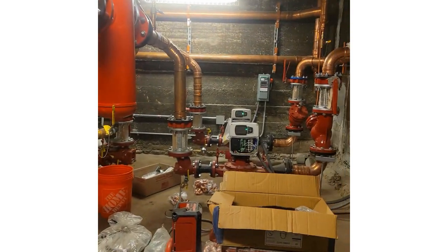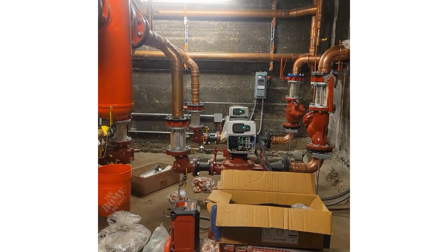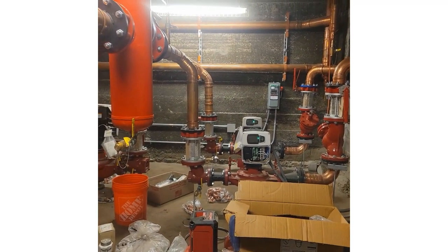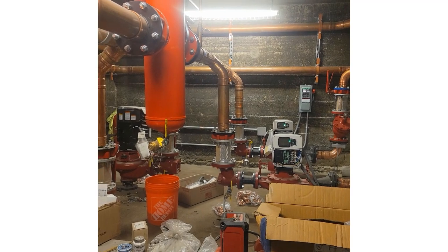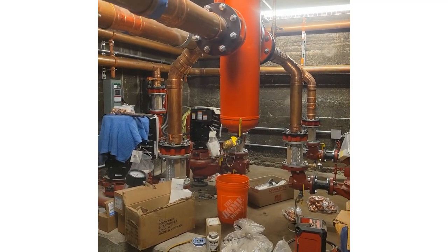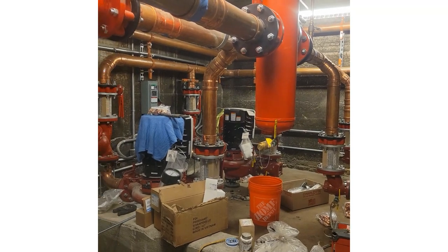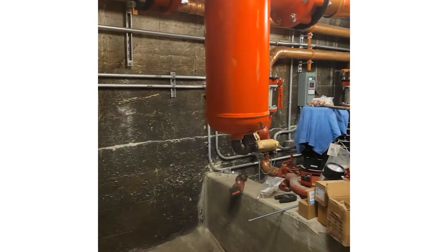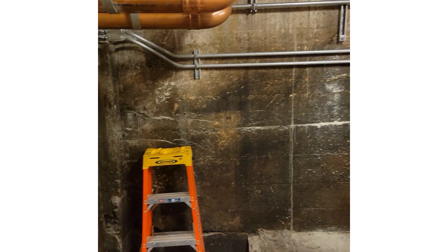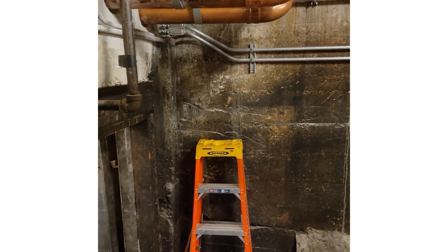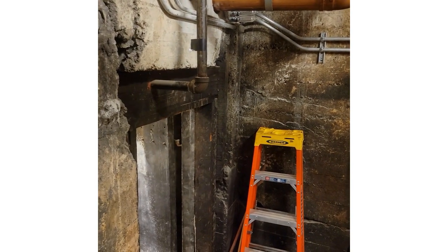You can see the pumps are actually put together, and the green lights there show they're in operation. We've been circulating them and then testing the chemistry to make sure the water is pure and has the right amount of antifreeze in it, so that next week we can start bringing up the air handling units, and after that, the geothermal heat pumps.